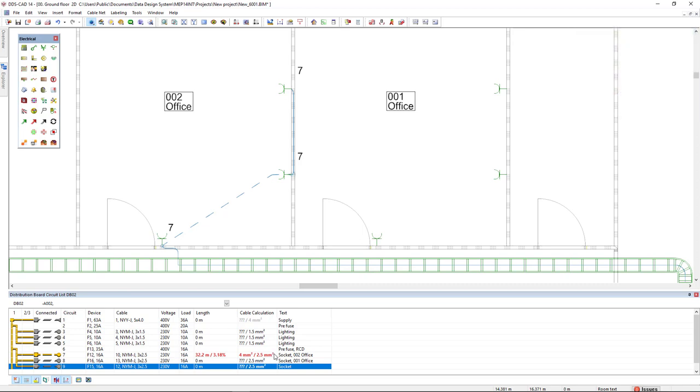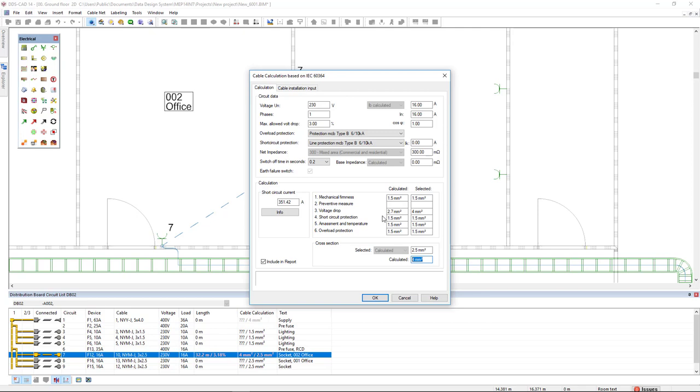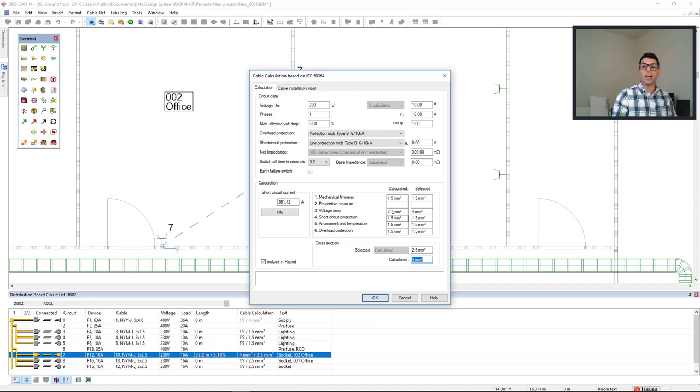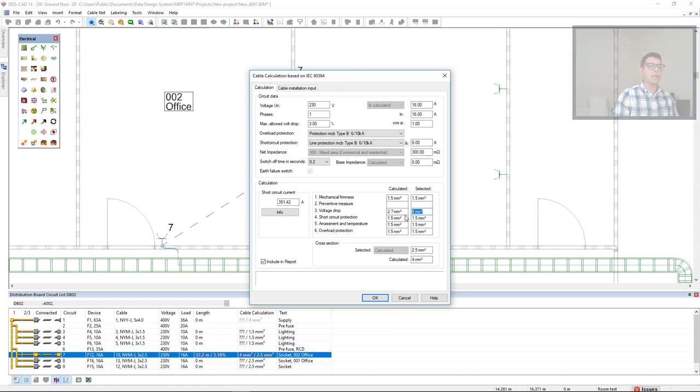If we double-click the cable calculation for the circuit seven, we see that the selected cross-section of 2.5 square millimeters also indicated here on the right and we also see the calculated cross-section of four square millimeters also indicated in the distribution board circuit list. And we have these results from the voltage drop. We see that DDS CAD calculates the cross-section from the voltage drop of 2.7 square millimeters. Since this value is not available as a cable size, DDS CAD gets the higher available cable size of 4 square millimeters.